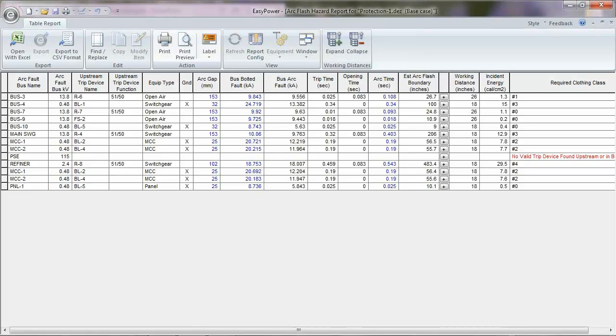From what I've heard, the IEEE 1584 is going to be requiring analysis on systems below 250 volts. But yeah, I could provide the template to anybody that wanted it, that main template that I had for shock hazard and arc flash. It looked like that might be something anybody would want, I could send that out, and you guys can play around with it however you'd like.